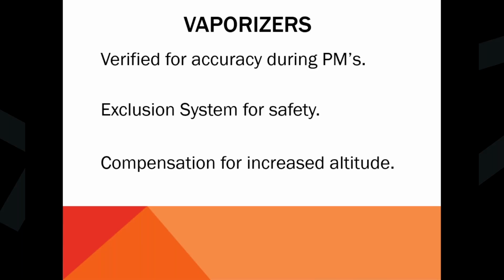One thing that folks at sea level probably aren't aware of or had to deal with is altitude. Say in Denver and higher, we actually have to compensate for the increased altitude, because anesthesia is less efficient at altitude than it is down at sea level. So when you're checking it, say at 4%, you may get like 3.4% or 3.5% as your reading. With the gas analyzer, they will give you a chart that tells you, based on altitude and what type of gas you're using, what that compensation is. Then they'll give you a number and you multiply it by your reading, and that will adjust for the difference between sea level and up at altitude.